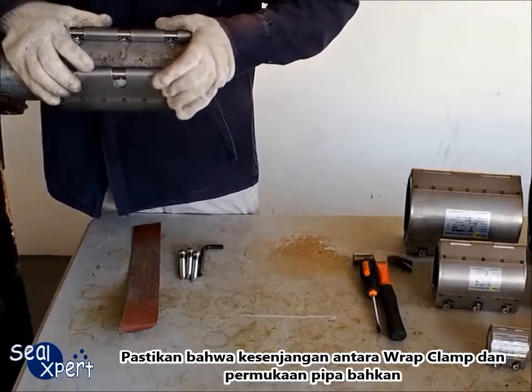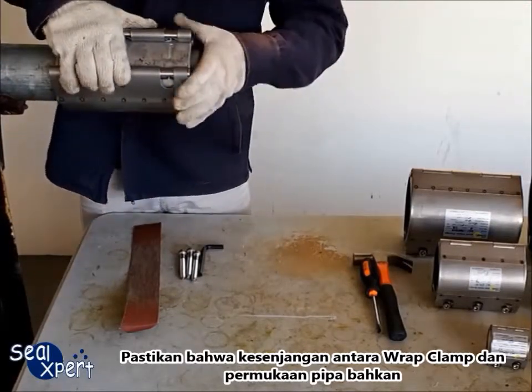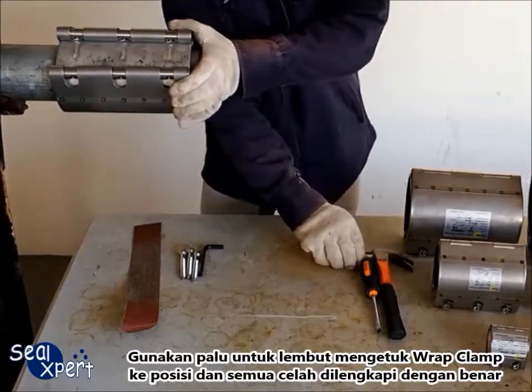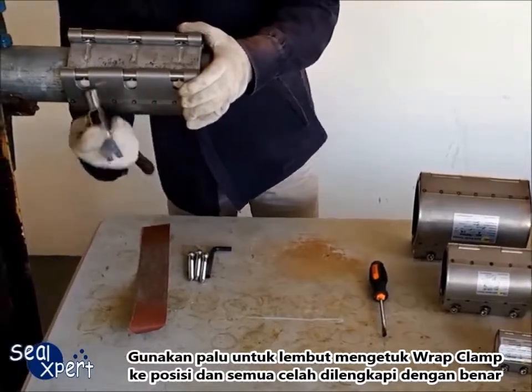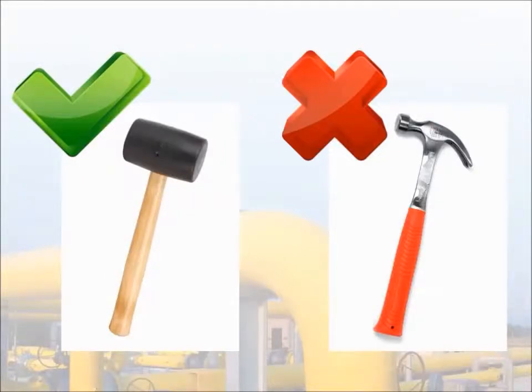Ensure that the gap between the Wrap Clamp and the pipe surface is even. Use a mallet to gently knock the Wrap Clamp into position, and ensure all gaps are fitted correctly. Do not use a hammer as this may deform the Wrap Clamp.